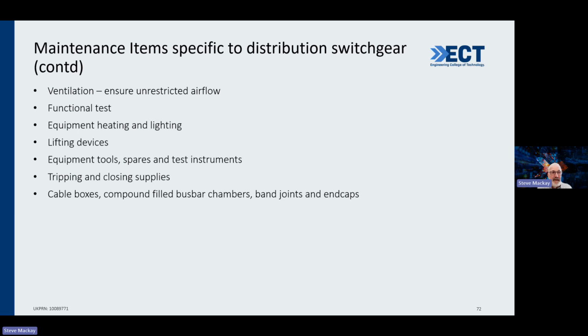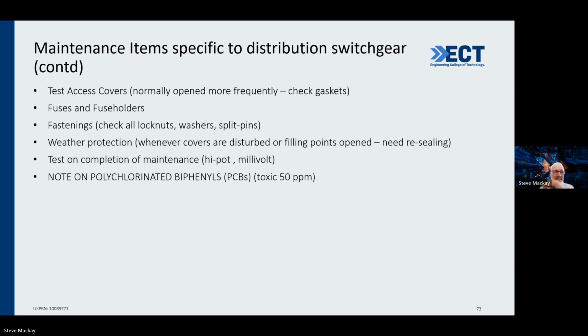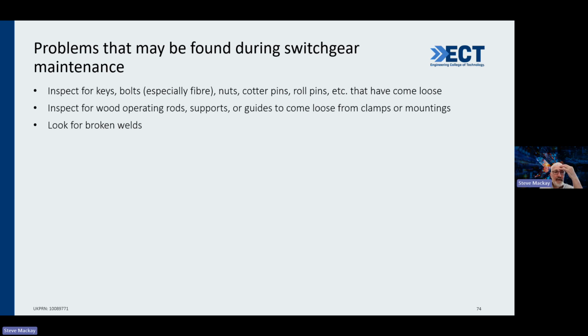Other items you need to look for, ventilation. Changes around the circuit breakers may result in restricted airflow, so you need to watch out for that. Functional test, lifting devices, equipment, tools, etc. So these are all sort of things you would be looking for. Test access covers, fuses and fuse holders, fastenings, weather protection, test on completion, and obviously PCBs, which obviously we don't want to have anything to do with.